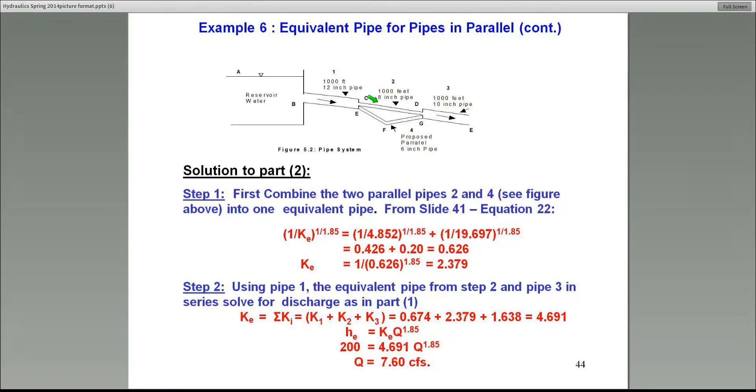What you want to do is first take these two parallel pipes and convert them into a single pipe. That KE is obtained by taking the reciprocal sum of the two pipes, two and four. Their KE values are K2 = 4.852 and K4 = 19.697. You take the reciprocal sum and get a KE of 2.379.